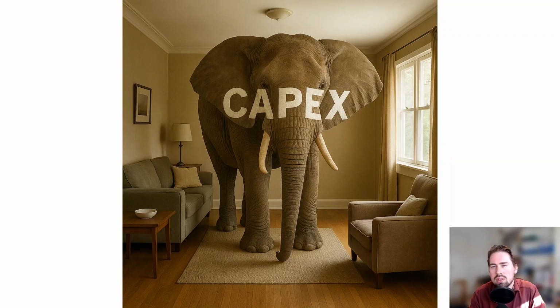So it's not even the case that in all situations a ground source heat pump is more expensive, but typically for a residential project, a single house, it is. But if you then, for example, again move towards a collective system where you can actually share the investment cost of your geothermal source, it might as well not be the case. So that was just something I wanted to say about the investment costs. Keep in mind that most probably it is a more expensive technology in investment cost, but it's not by definition the case. And that's an important nuance that's sometimes missing in this debate.